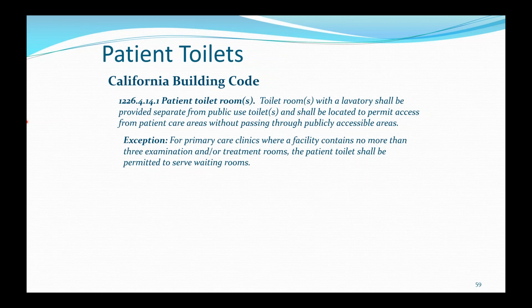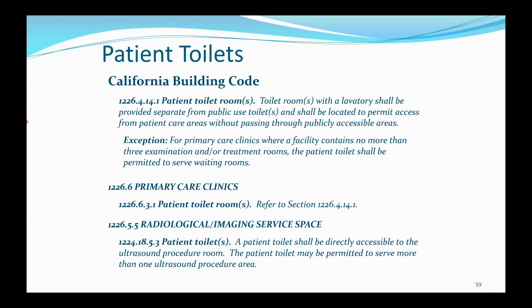If the primary care clinic is very small with 3 exam rooms or less, the patient toilet may be permitted to serve waiting rooms. Primary care clinic patient rooms must have patient toilets in the primary care clinic care spaces. And if you have imaging services, those also require patient toilets to be directly accessible to the ultrasound procedure room, and it is allowed to share between more than 1 procedure room. Typically, we see a kind of Jack and Jill, where there's 1 toilet flanked on each side by an ultrasound procedure room.